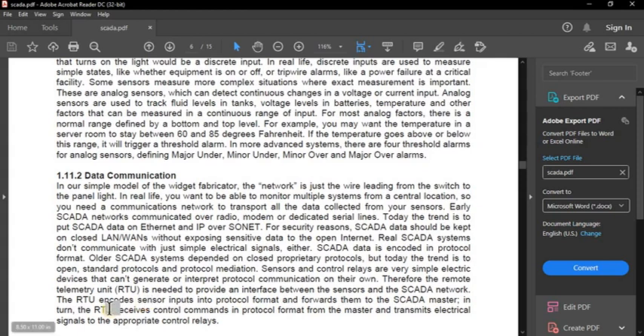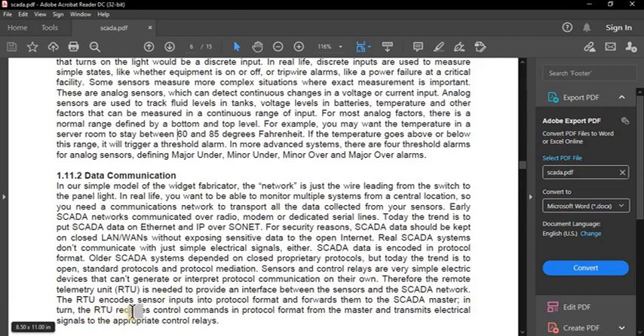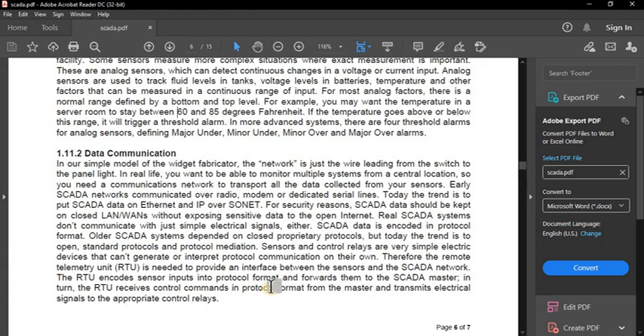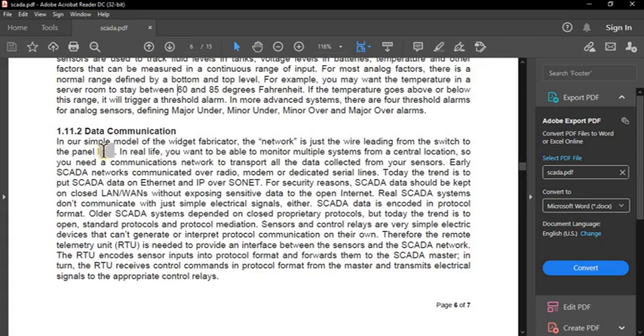The RTU encodes sensor inputs into protocol format and forwards them to the SCADA master. In turn, the RTU receives control commands in protocol format from the master and transmits electrical signals back to the appropriate control relays. This is what is performed in data communication using RTUs and SCADA.